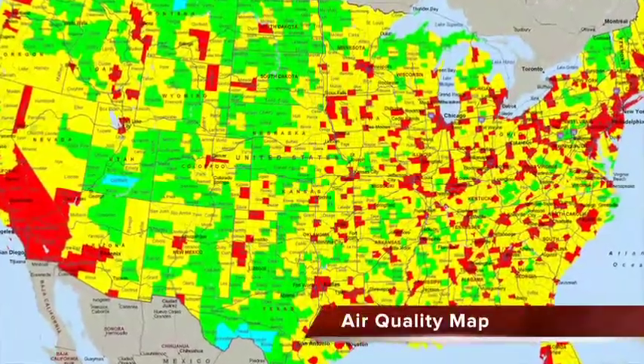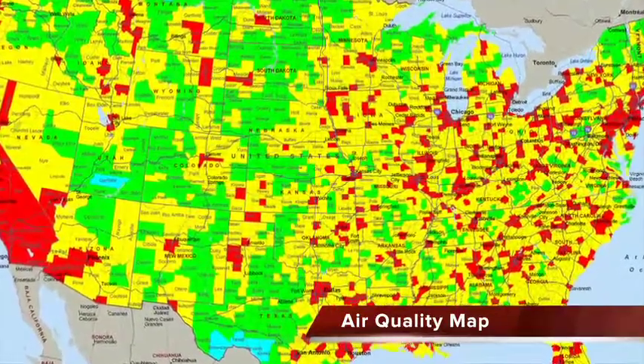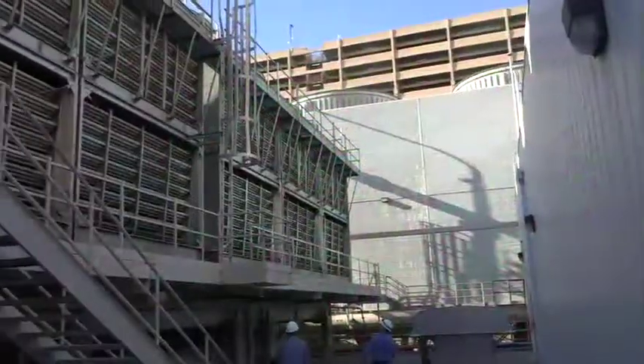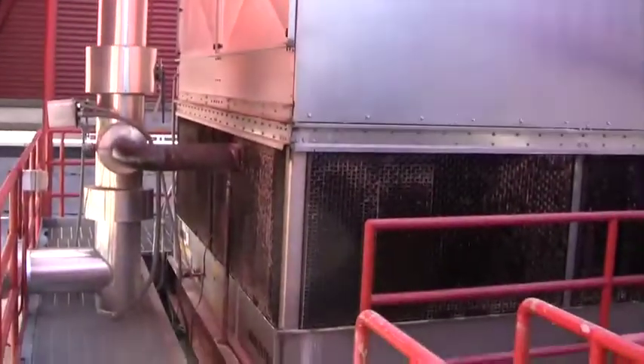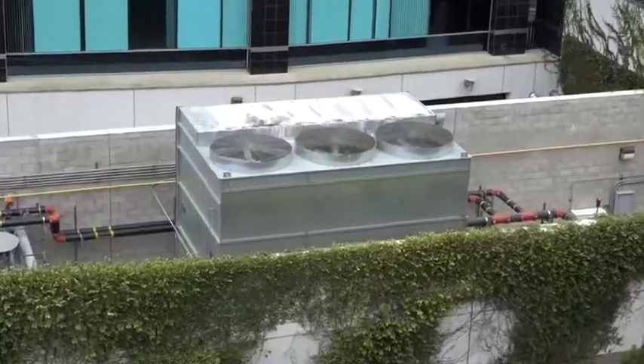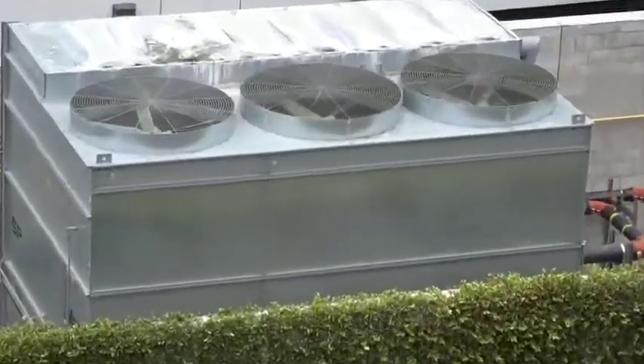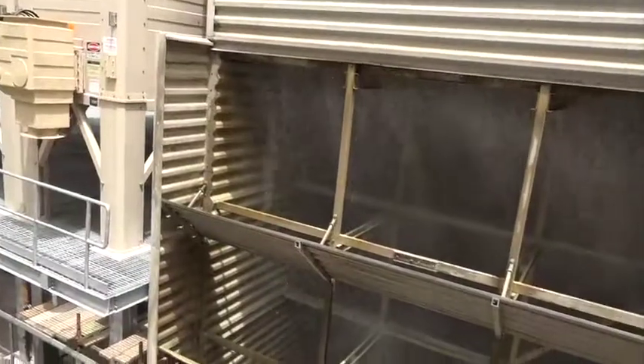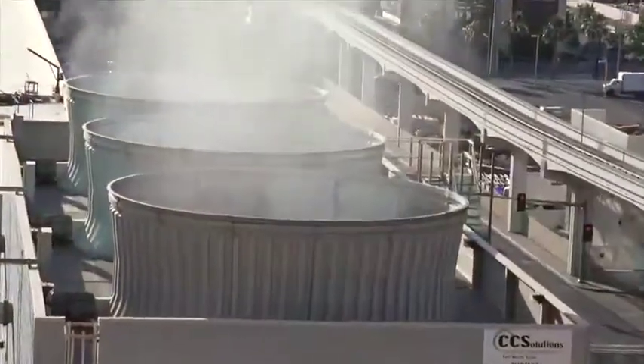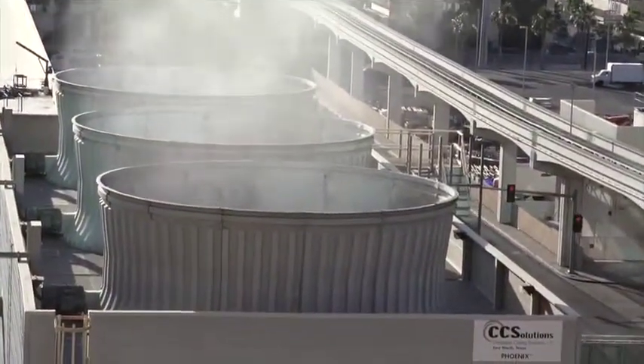Drift emissions can even be classified as PM10 emissions by the EPA and be an important factor in environmental permitting for industrial plants. Even though it's a small fraction of the circulating water flow, a conventional 1,000-ton cooling tower that would support a larger building can routinely spray out over 200 gallons of these drift emissions daily.